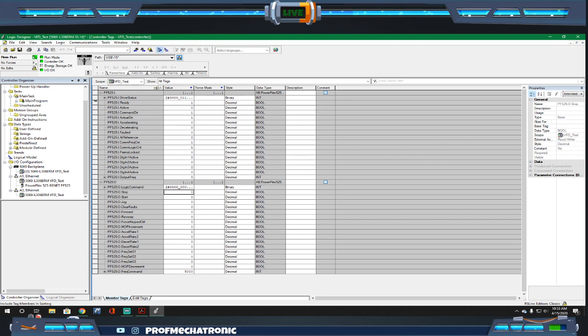So that's the basics of setting up a VFD over Ethernet IP, or more specifically, a PowerFlex 525 to a 5069 L306 ERM. We're able to actually have that VFD commanded and controlled from the PLC over the Ethernet protocol and able to do and configure a lot of that information.